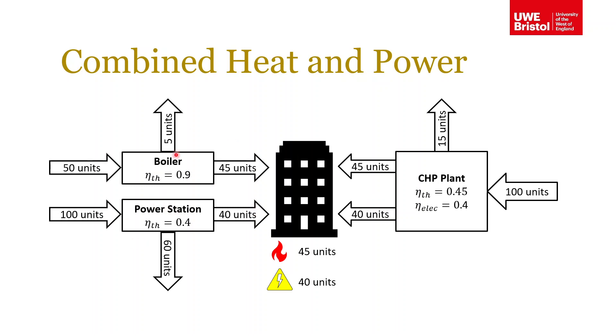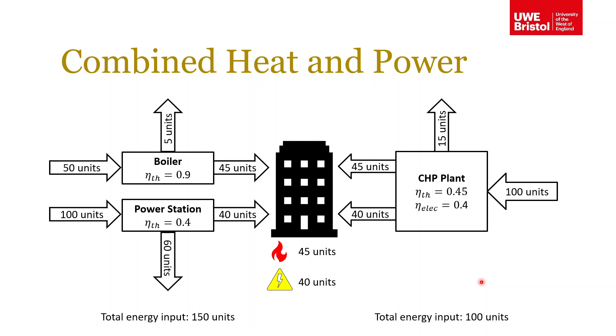Comparing the conventional system to the CHP plant: for the conventional system we're inputting 150 units of energy to get a total of 85 units supplied to the building, whereas with the CHP plant we're only putting in 100 units. The combined heat and power plant is therefore more efficient than getting heat and power from separate sources — that's the important point to consider here.